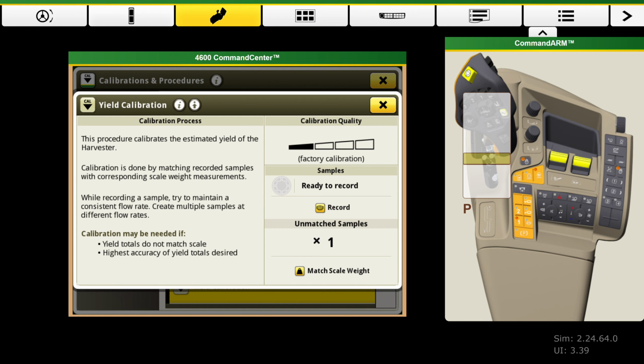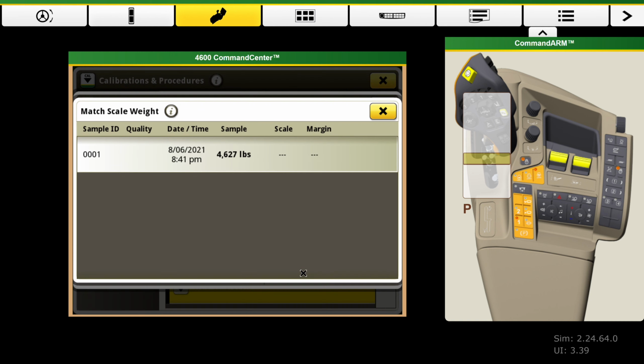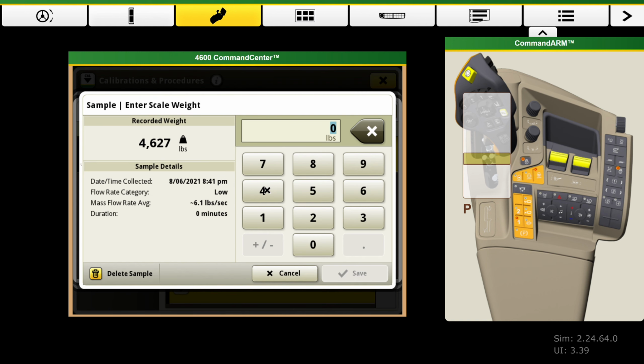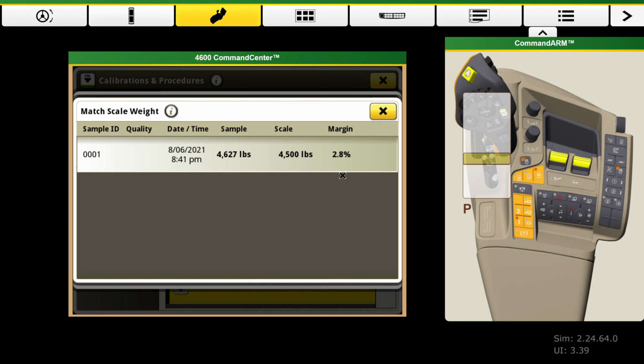You can then see we have one unmatched sample. We can press Match Scale Weight, select Scale, and then type in the actual weight from a certified scale. Select Save. We can see that load was 2.8% error.